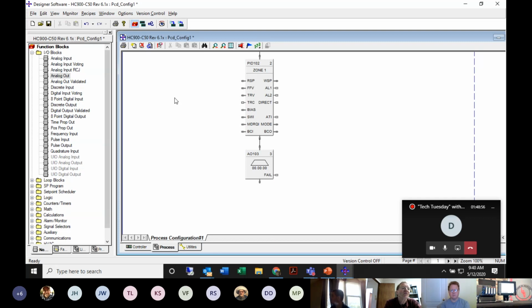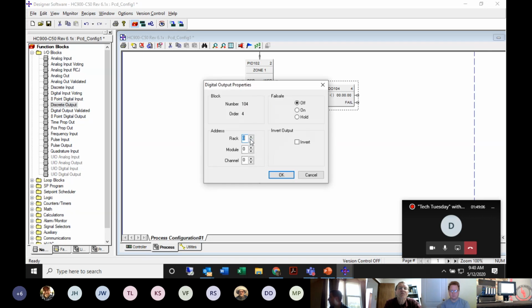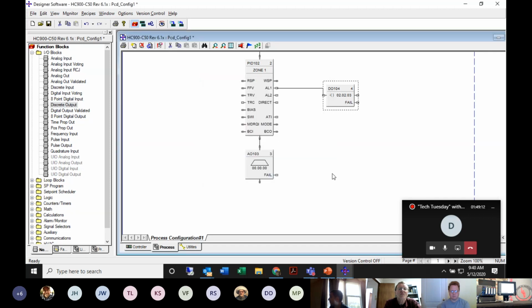So if I want to tie my alarm to a discrete output on the HC, I can click on discrete output, take my alarm 1 over to the discrete output, and now if I double click on it, I can tell exactly where that discrete output is connected into my I/O rack.